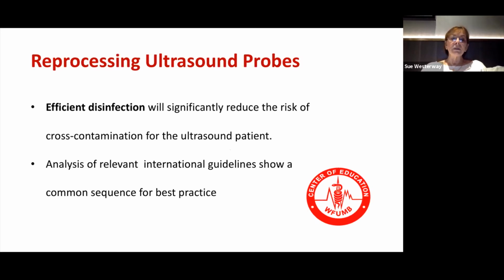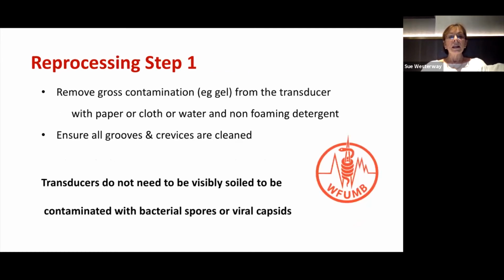An analysis of the relevant international guidelines shows a common sequence for best practice. Number one is to remove the gross contamination, such as the gel, from the transducer. We do this by using paper or cloth, or even water with a non-foaming detergent. We need to ensure that all grooves and crevices are cleaned, because transducers do not need to be visibly soiled to be contaminated with those bacterial spores or viral capsids.